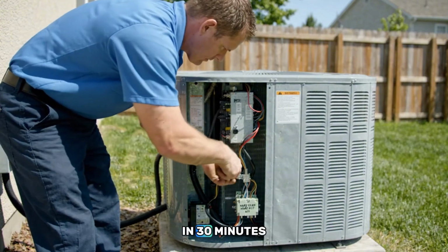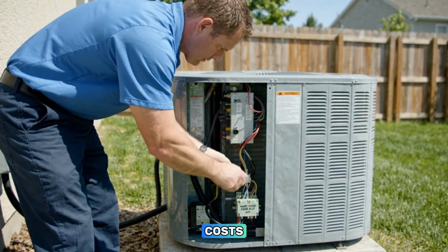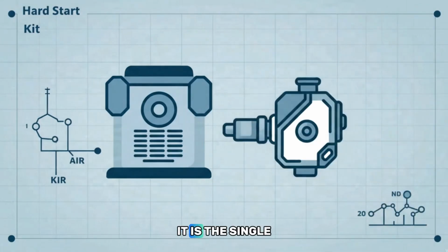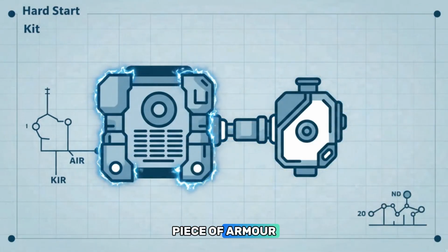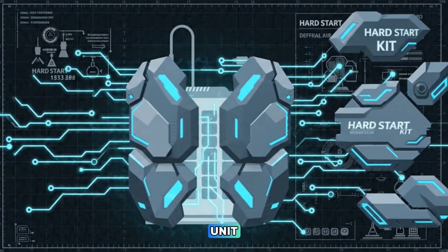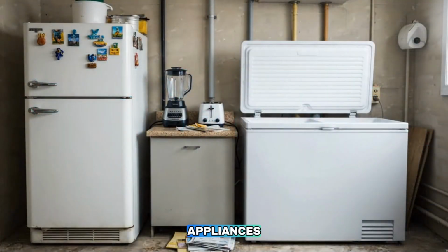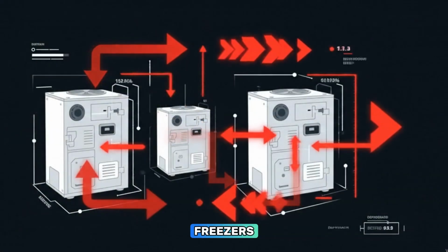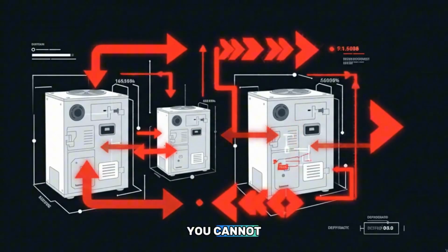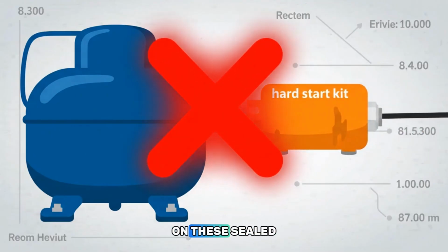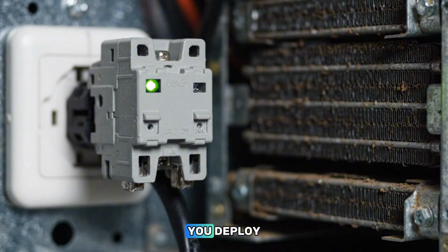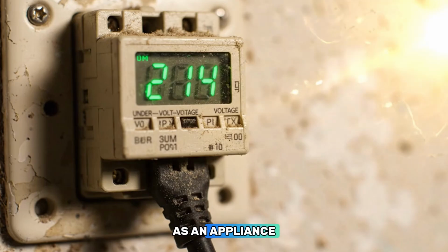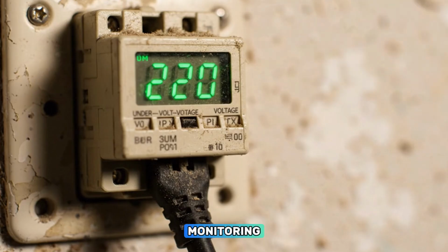Any licensed HVAC technician can install one in 30 minutes. The hardware costs less than $50. It is the single most effective piece of armor you can buy for a central air unit. For your smaller appliances, refrigerators, and deep freezers, the strategy shifts. You cannot install hard start kits on these sealed units. Instead, you deploy an undervoltage protection relay, often marketed as an appliance surge protector with voltage monitoring.